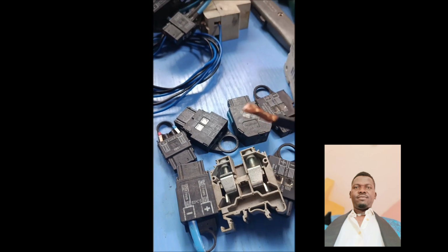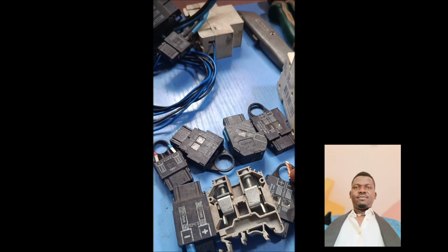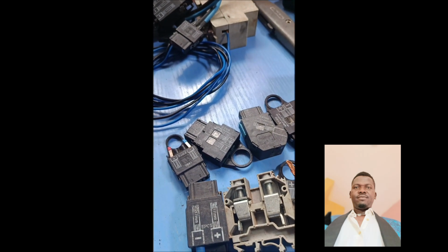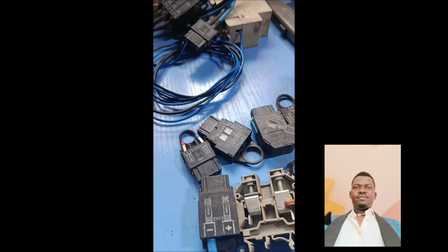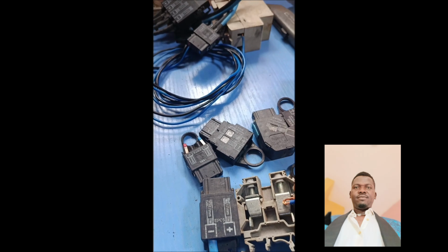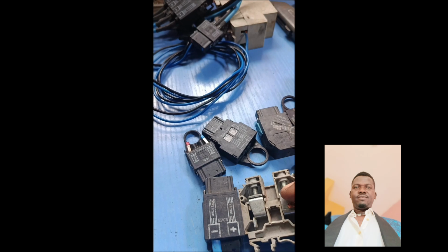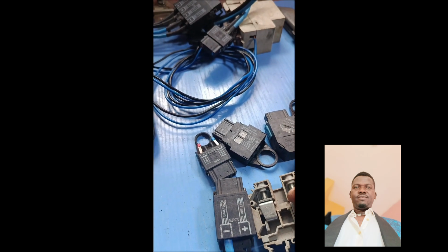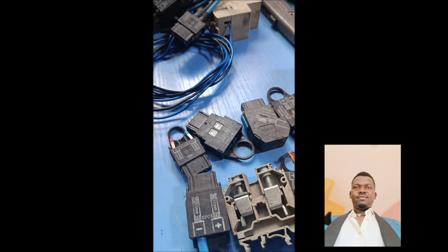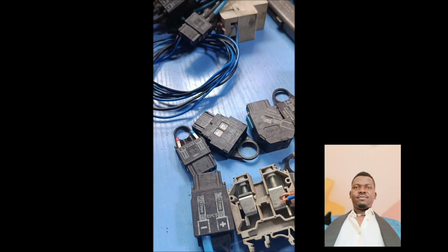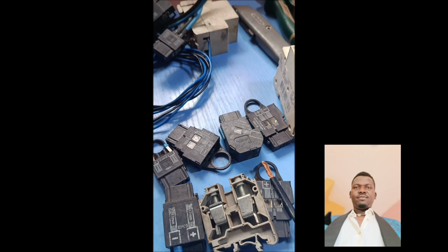Another one is using a less sizable cable. For example, connecting a water heater using 1 mm, and you said you followed all the steps, and you made sure the connector tied well, the contacts, the metal part, is well tightened, and the pair conductor is the only thing inside there, and you still have a burning cable. When you use an undersized cable, it will happen. So you have to make sure your cable sizing is considered also.